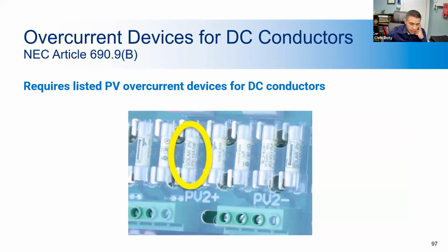Here we have a correct example of how things were installed correctly, but we talked about having the correct equipment for the application. So all the conductors and fuses should be DC rated and should be rated for PV. And you can see here, this is rated for PV.